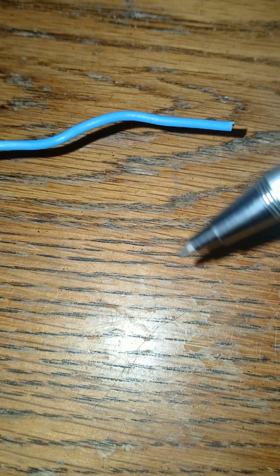So the blue color, the question is, what does the blue color do? The blue, generally speaking, not always, not universal, but generally accepted, is considered the common. So you have a red power wire, 24 volt, that comes in, then you have a blue common wire. The common wire goes back to most of your fixtures, so to my way of thinking, it's kind of a return wire.